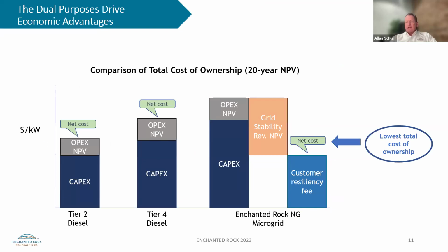The reason this isn't such a common practice is that backup generators are pretty low cost. For data centers, they're a standard cost of doing business. This gives you a relative scale of the price of tier 2, from a capital expenditure standpoint plus operating expenditure, on a net present value over 20 years. The net cost of backup power is indicated by the top of the bar on the left. For tier 4, it's more expensive, mostly because CapEx is higher—that extra pollution control adds cost to the generator, and it's also a bit more expensive to maintain every year. A natural gas microgrid is more expensive yet.